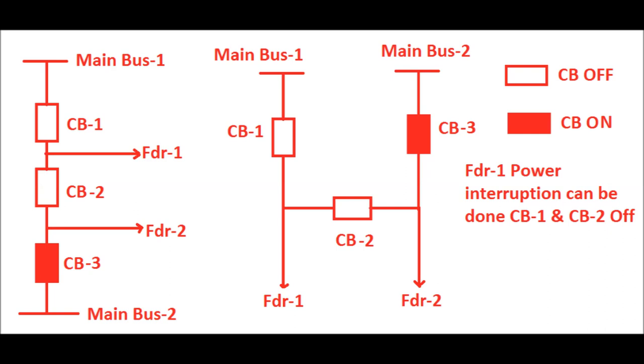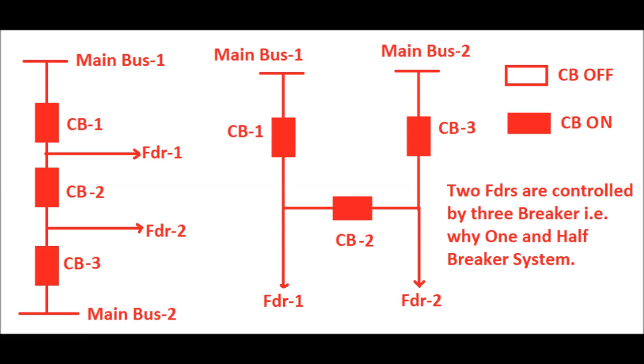When feeder 1 and feeder 2 are in running condition, all three circuit breakers are in closed positions. If feeder 1 power must be interrupted for maintenance — that is, a shutdown of feeder 1 — then CB1 and CB2 should be switched off. Similarly, we can take a shutdown of feeder 2 or interrupt the power through feeder 2 by switching off CB2 and CB3. So switching operations of feeder 1 and feeder 2 are controlled by three circuit breakers via main bus 1 and main bus 2.